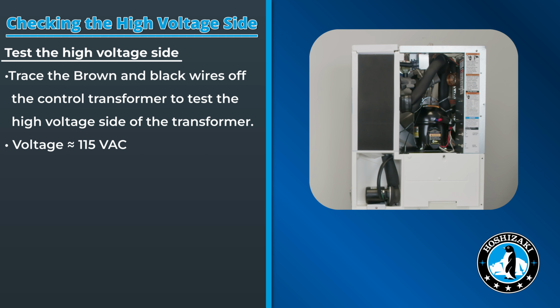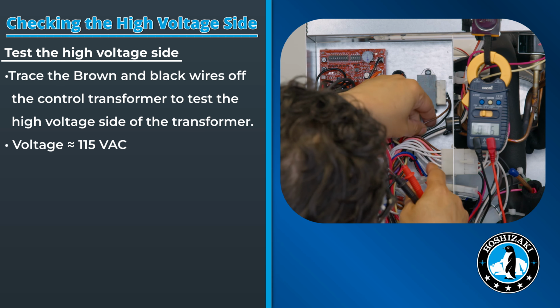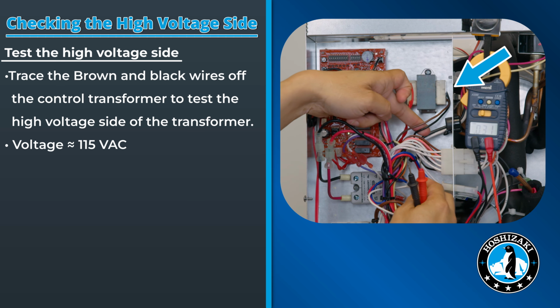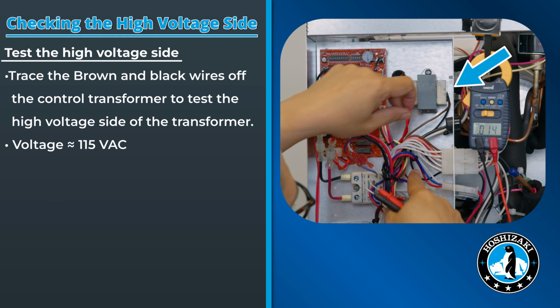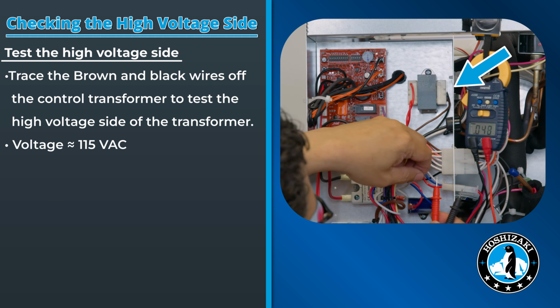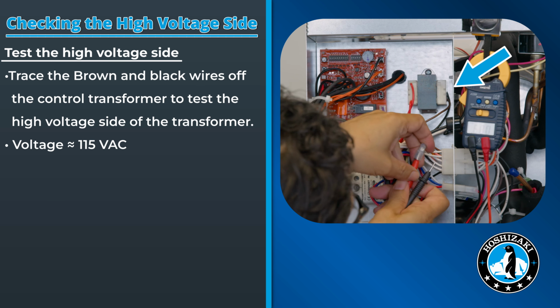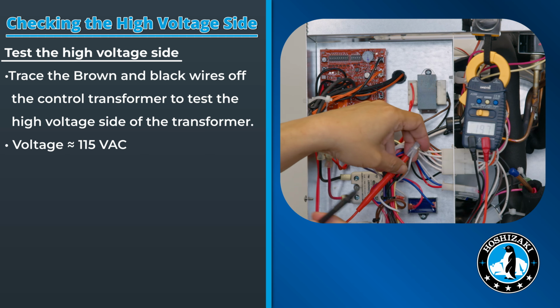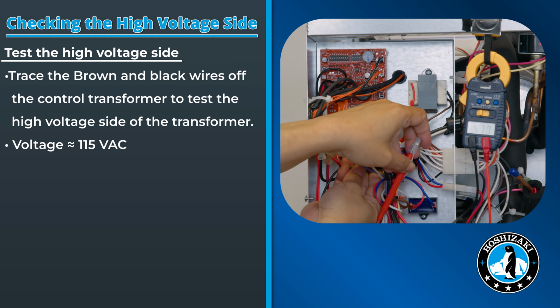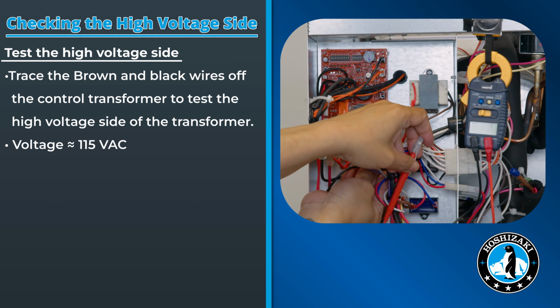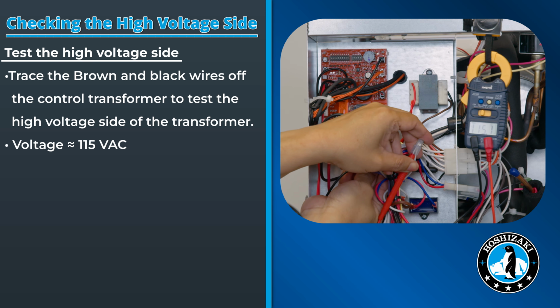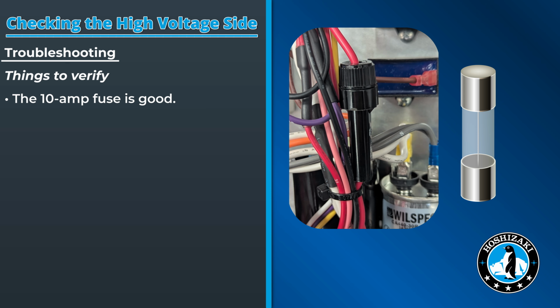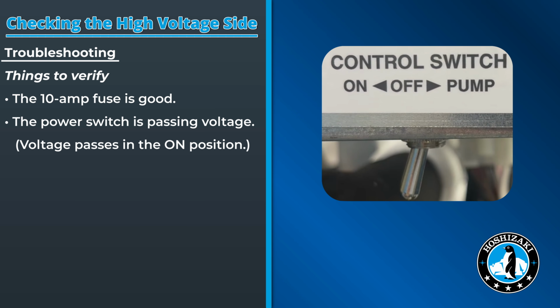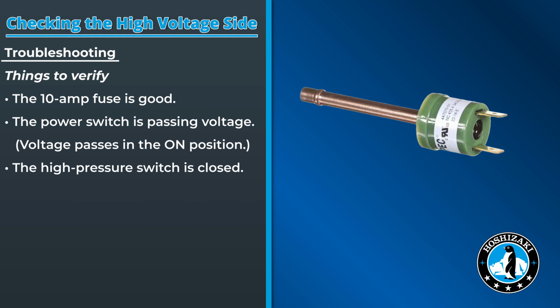Now that we verified the correct voltage entering the machine, we'll move over to the control box and test the high voltage side of the control transformer. Trace the black and brown wire from the transformer to find an easy access point to check voltages. The voltage across these wires should be approximately 115 volts. If the voltage is incorrect, verify the following. The 10 amp fuse is good. The power switch is passing voltage. The high pressure switch is closed.